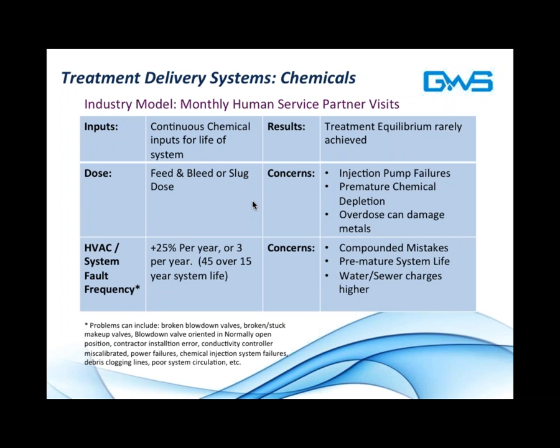The challenge is, under chemical treatment, that if a service partner shows up on January 1st and the makeup or blowdown valve sticks either open or closed on the 2nd, then that cooling tower is effectively without effective treatment, or under a state of crisis, for the next 29 days until the service partner returns. What this means is their mistakes are compounded, the mistakes that have occurred as a result of system operation mistakes, and therefore you end up getting this accretion in problems within the system. So you have premature system life, and you end up ultimately wasting significant amounts of water.